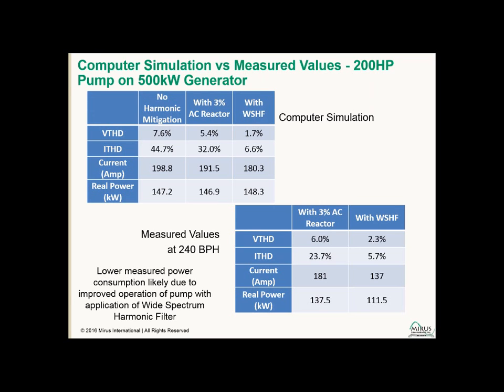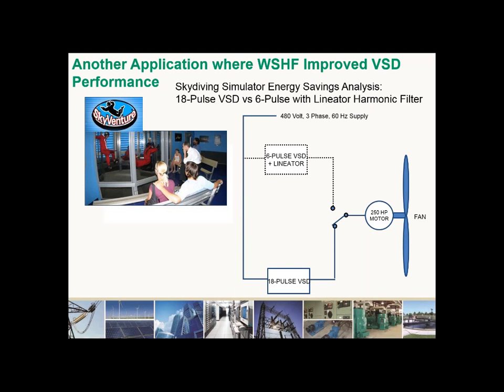We've run into this situation before. I'll give you an example here. This is a skydiving simulator ride, where this one was located in Orlando, Florida. Our customer wanted to prove to the owner of the skydiving simulator ride that if they replaced their 18-pulse drive solution with a 6-pulse drive and our filter, there would be a substantial reduction in the power consumption.